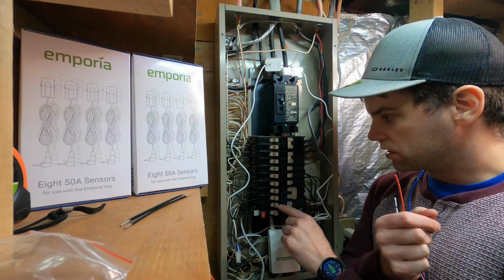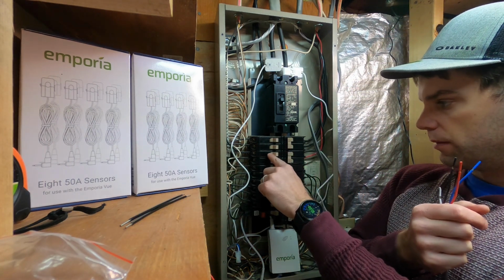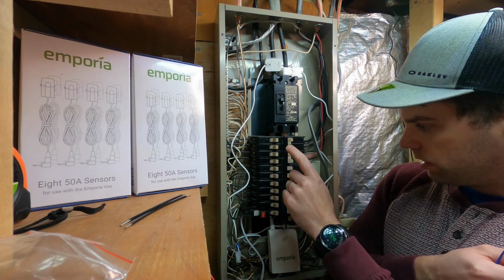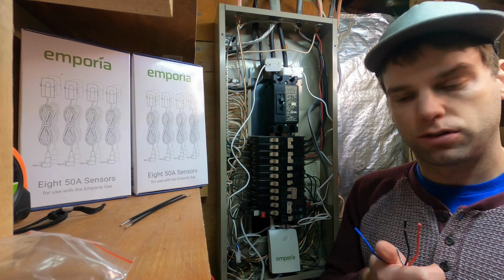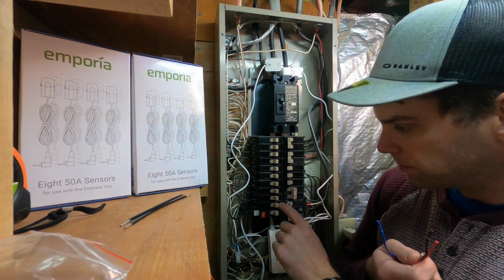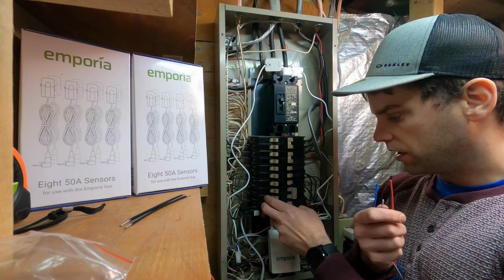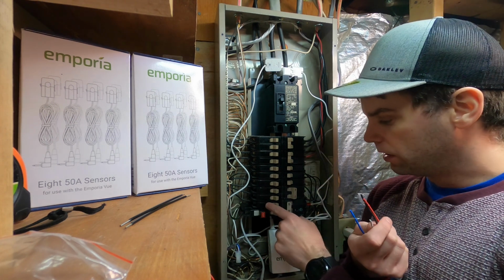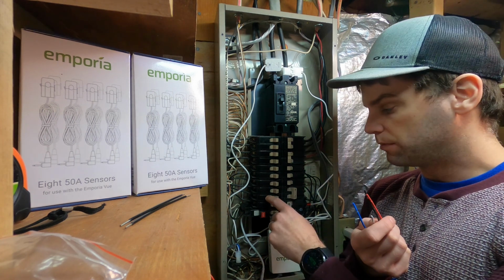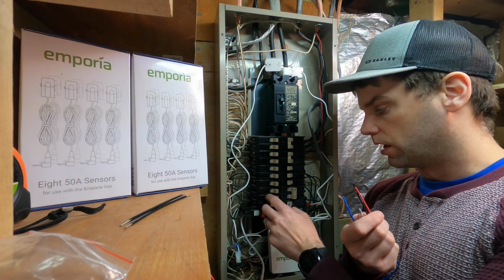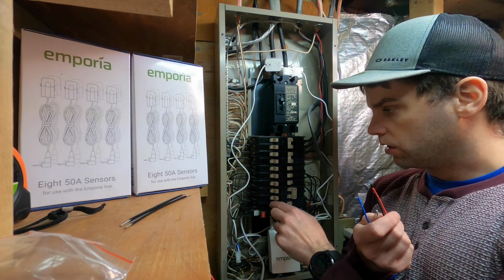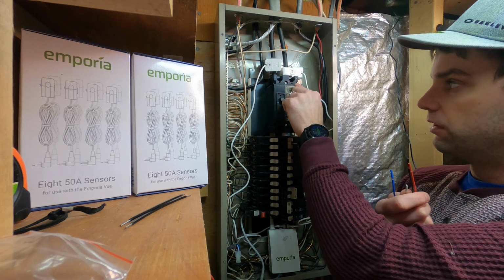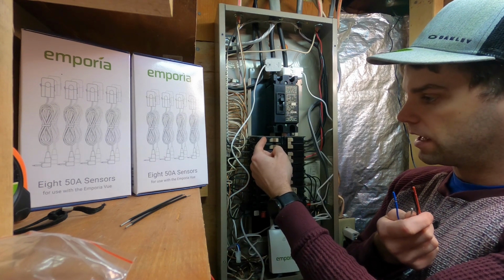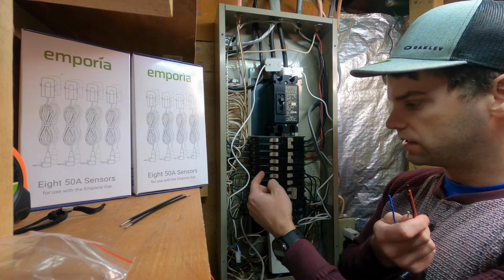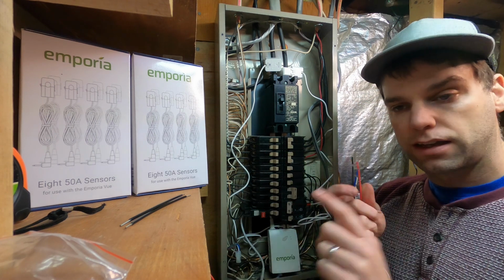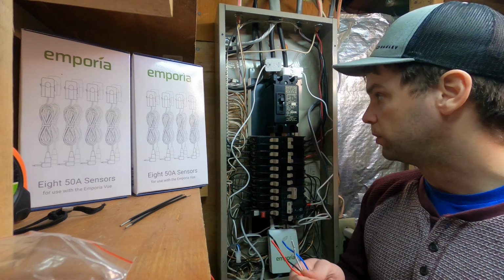So what I'm going to pick, you can see I've got a 20, a 20, a 20 up at top. I've got a 50 for my stove, a 30, another 30, 30, but everything else in my panel is 15. Oh, I got one more 20 down here for the garage. So I'm going to pick these two breakers here because I don't want to go on the GFI. The GFI is also 20 amp. It's really important that they be right on top of each other, or an even number of spaces away, because the way this works is I've got two rails, right? 120 volts here, 120 volts here. So this is phase A, phase B, phase A, phase B, phase A, phase B. The way that they clip into the bus bars in the back is going to be alternating back and forth for phase A and phase B.